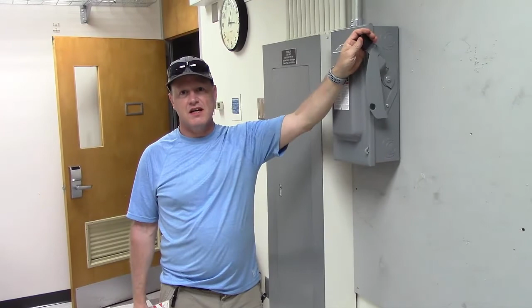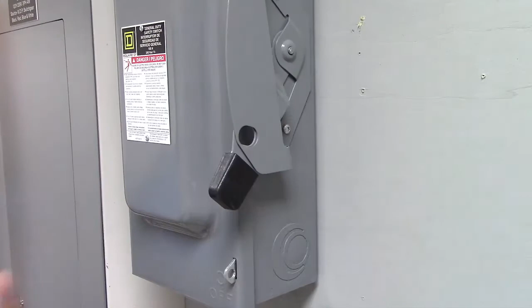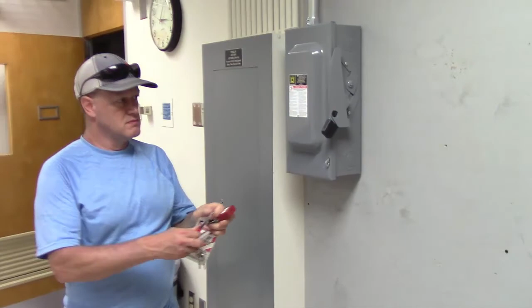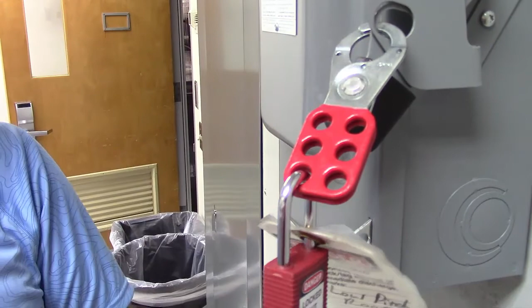1C, lock out the building grid service panel. This disconnect provides the power for our electrical sub-panel that all of our solar arrays are connected to. So we're going to shut this off so we can work in that sub-panel safely. Once we shut it off, we use Lockout Tagout in order to make sure that it stays off while we're doing that work. So we have a lock that has only one key, and we put it on the disconnect and hold on to the key so that this cannot be turned back on until we're ready for it to be turned on.